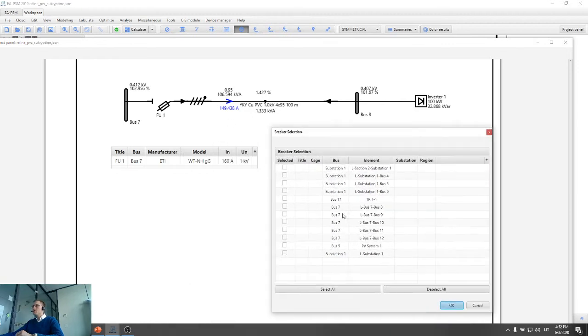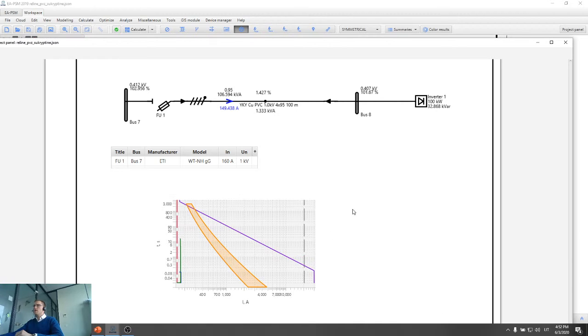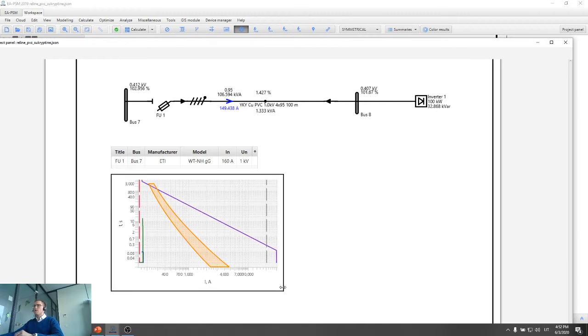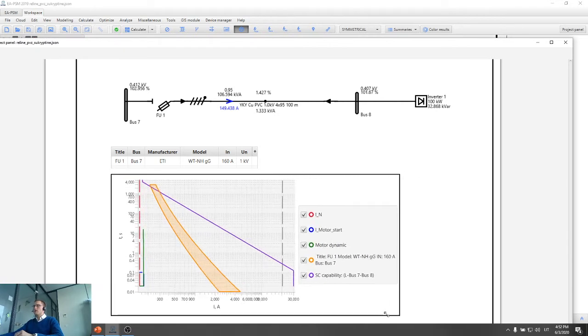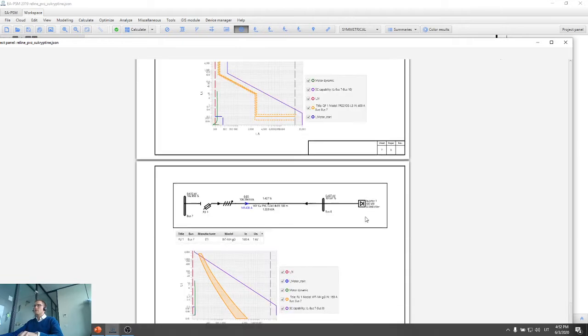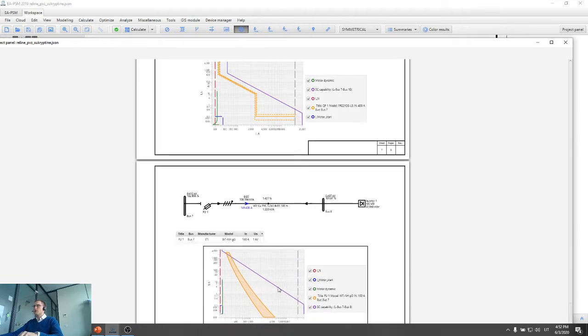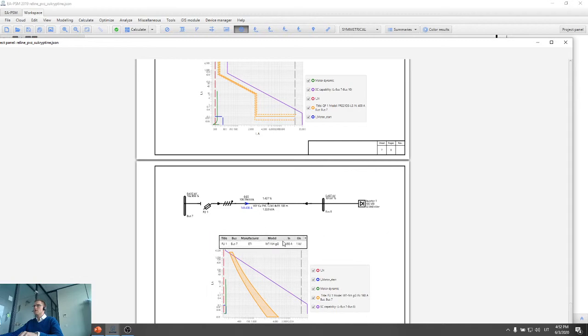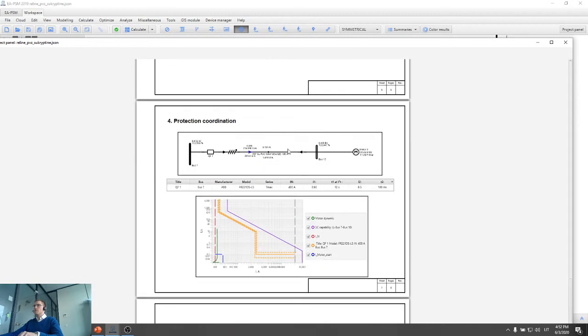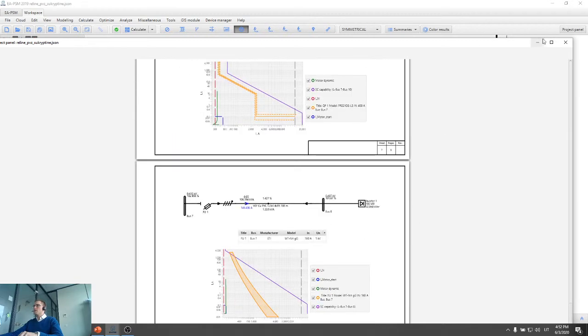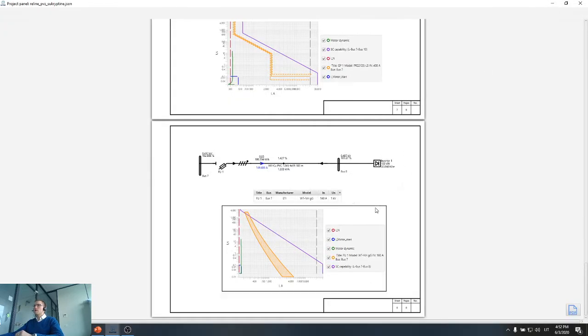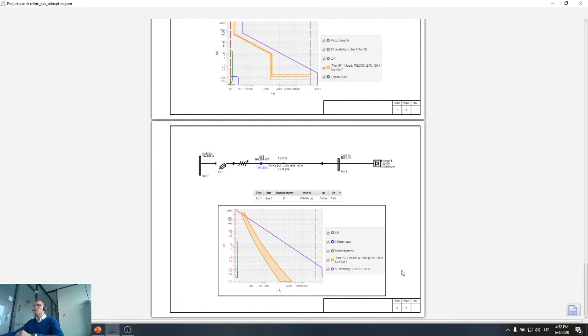I can also add the fuse curve. So bus 17 and line name bus 7, bus 8. So from the list here, this is the breaker. Yeah, so this is the fuse curve. So I can increase the characteristic of the fuse. I can align it so that it's in the same location as this one, and basically one by one I can create the report about all the protections.